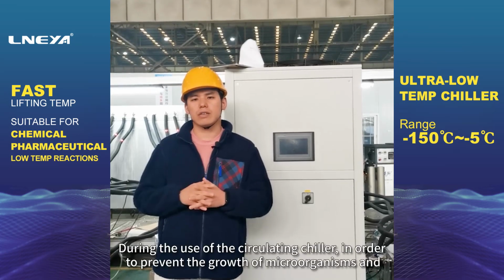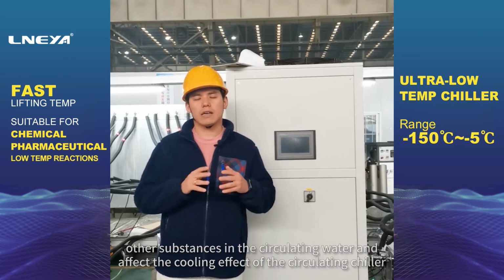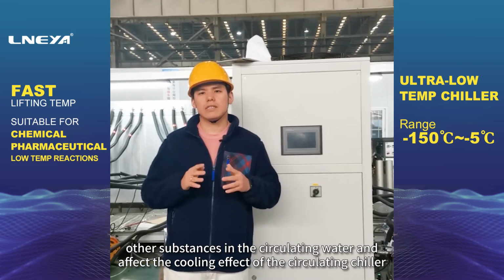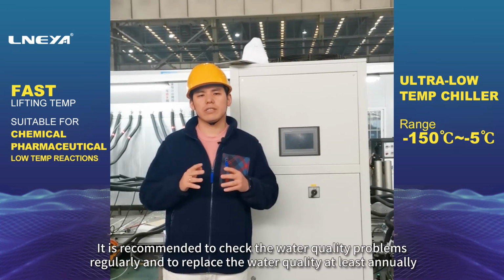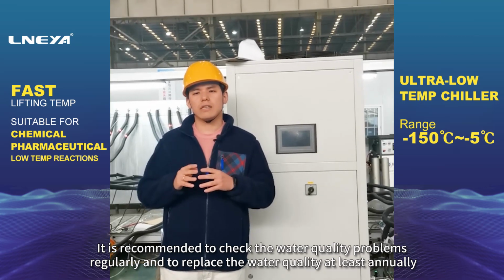During the use of the circulating chiller, in order to prevent the growth of microorganisms and other substances in the circulating water and affect the cooling effect of the circulating chiller, it is necessary to pay attention to water quality issues. It is recommended to check the water quality regularly and to replace the water at least annually.